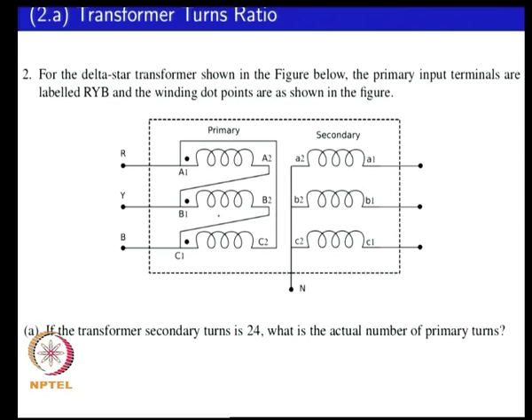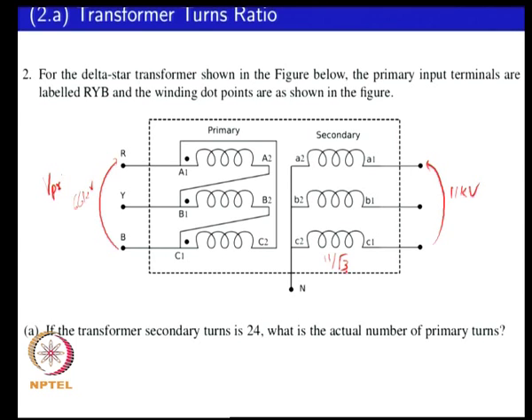The next problem is about a delta-y transformer. Your primary voltage is 66 kV and your secondary voltage is 11 kV on a line-to-line basis. If you look at your secondary which is Y, your voltage on your winding is 11 divided by root 3. The first question is to calculate what your primary turns would be if your secondary turns is 24, so you have the turns ratio.